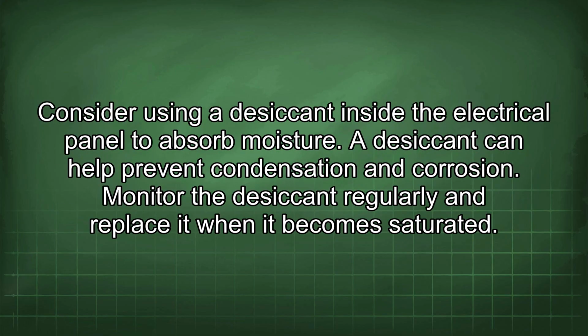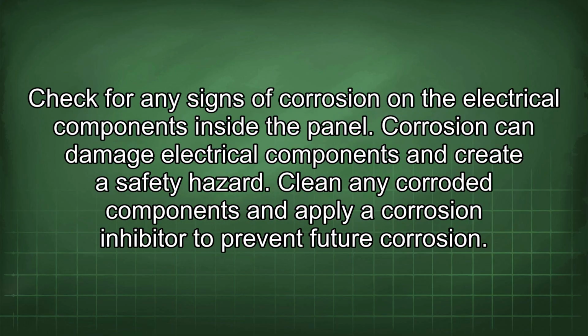Consider using a desiccant inside the electrical panel to absorb moisture. A desiccant can help prevent condensation and corrosion. Monitor the desiccant regularly and replace it when it becomes saturated. Check for any signs of corrosion on the electrical components inside the panel. Corrosion can damage electrical components and create a safety hazard. Clean any corroded components and apply a corrosion inhibitor to prevent future corrosion.